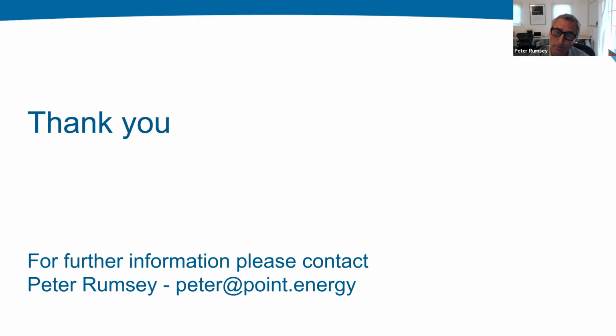Some older buildings use steam, and heat pumps are not good at making steam—don't even go there. The only way to make steam with electricity is an electric resistance boiler, which I'm not a big fan of. At Stanford, at high expense, they converted their steam system to hot water so they could use heat pumps, which work best in the 120 to 140 degree range. Some buildings were designed for peak temperatures of 160 or 180, so that needs to be considered. But many buildings are over-designed, so bringing the temperature down to 140 on the coldest day will often still be fine.